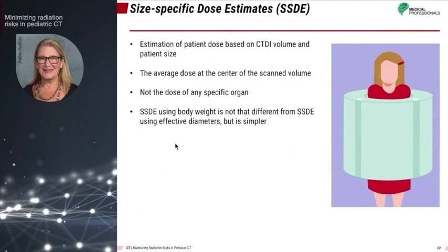In their report, Size-Specific Dose Estimates, or SSDE, in pediatric and adult body CT scans, the American Association of Physicists in Medicine Task Group 204 defined SSDE simply as a patient dose estimate which takes into consideration corrections based on the size of the patient, using linear dimensions measured on the patient or patient images.